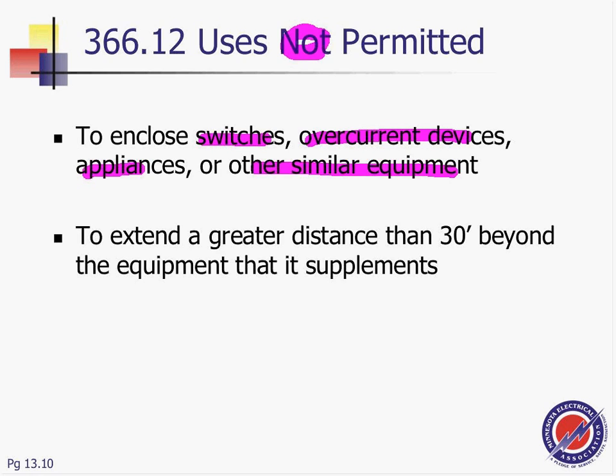Very interesting. I don't know if you guys remember when I talked about it, I said there's a limitation of 30 feet. You cannot extend the gutter more than 30 feet. 30 feet is an eternity. It takes a lot of wires. So you can't put an overcurrent protection device in it, or a disconnect or similar equipment. It's not meant to be a panel. Anything else about this? And you said the difference between the gutter and the wireway? Anything about this?